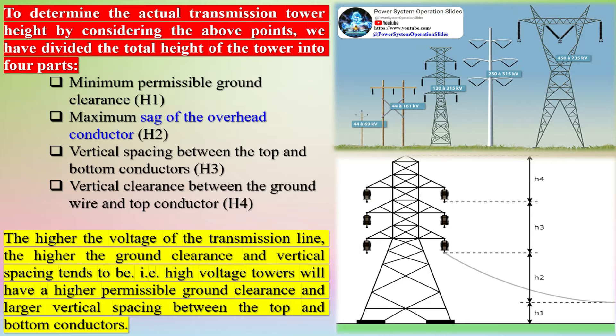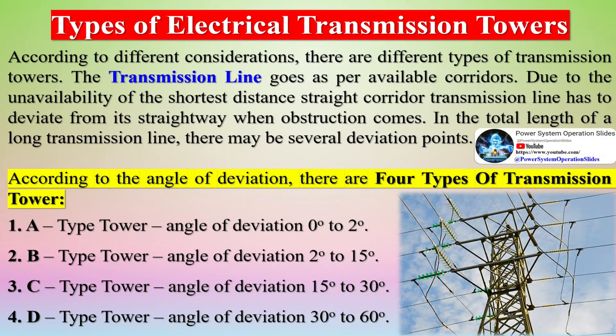To determine the actual transmission tower height, the total height is divided into four parts: H1 — minimum permissible ground clearance; H2 — maximum sag of the overhead conductor; H3 — vertical spacing between the top and bottom conductors; and H4 — vertical clearance between the ground wire and top conductor.